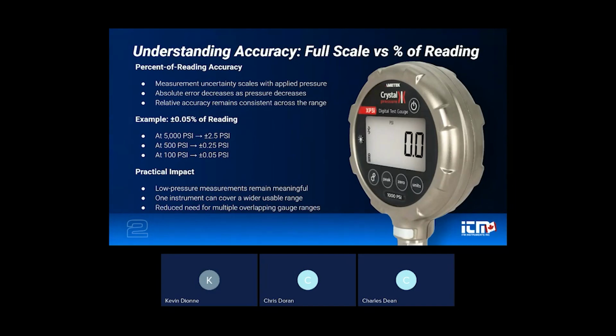The key takeaway of this section is percent of reading accuracy aligns measurement uncertainty with actual operating pressure, making it far better suited for applications where pressure varies significantly across a wide range. If you're working in an application where you're maintaining a fixed reading and it's close to the full scale of your instrument, then full scale accuracy could be the choice for you. So I just wanted to explain the difference between those two. Those are questions that we often get. If you have any questions on that, I can answer them at the end of the webinar. It's important that you understand that.